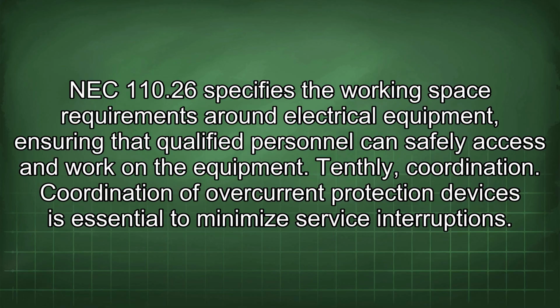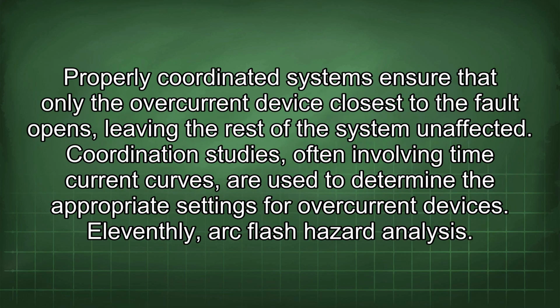Tenthly, coordination. Coordination of overcurrent protection devices is essential to minimize service interruptions. Properly coordinated systems ensure that only the overcurrent device closest to the fault opens, leaving the rest of the system unaffected. Coordination studies, often involving time current curves, are used to determine the appropriate settings for overcurrent devices.